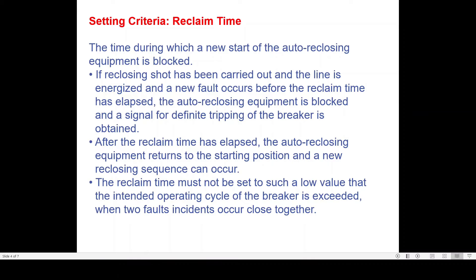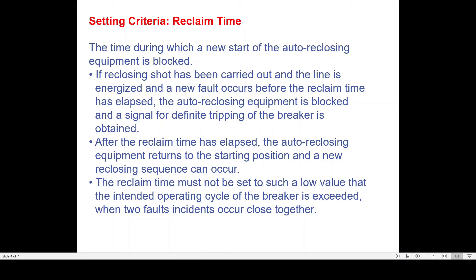The second thing is reclaim time. Reclaim time is basically the time during which a new start of autoreclosing equipment is blocked. Suppose R phase to ground fault occurs — your distance protection relay issues a trip command to R phase, and after one second the autoreclosure relay closes the circuit breaker. After this closing, the first autoreclosure cycle is complete.